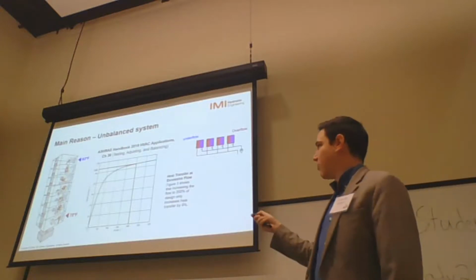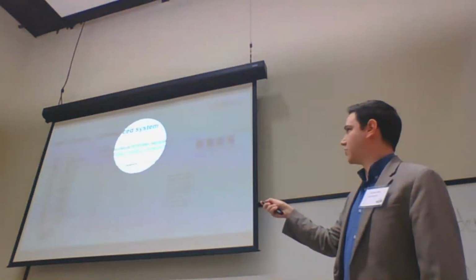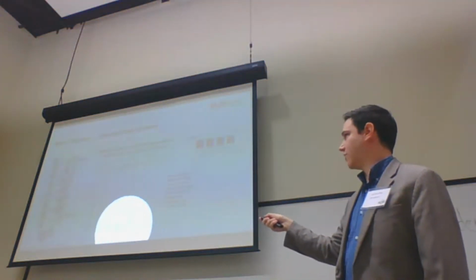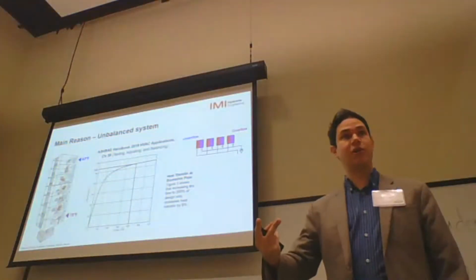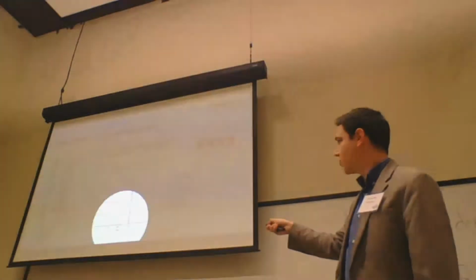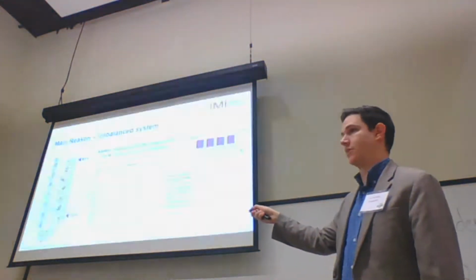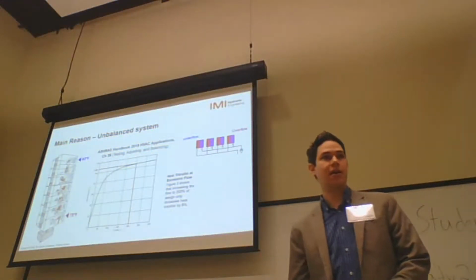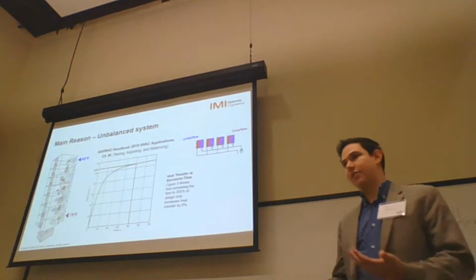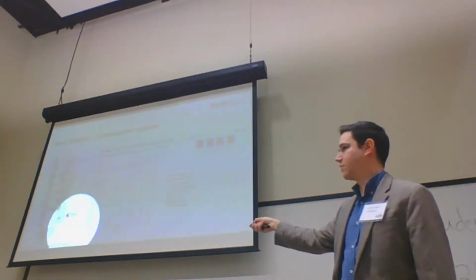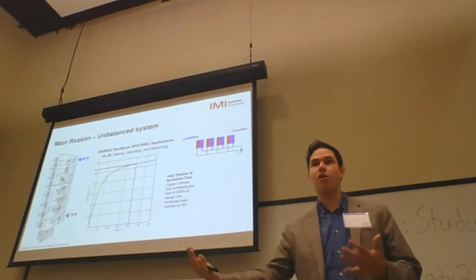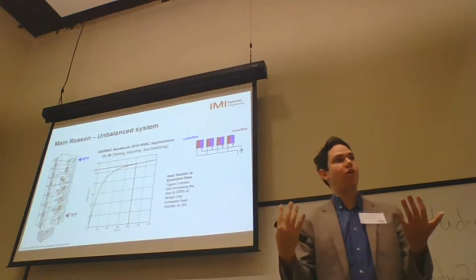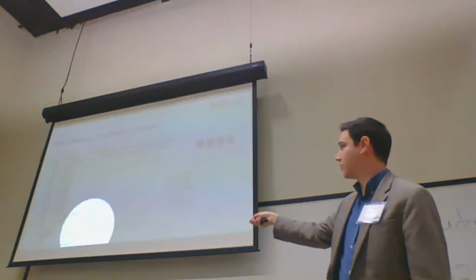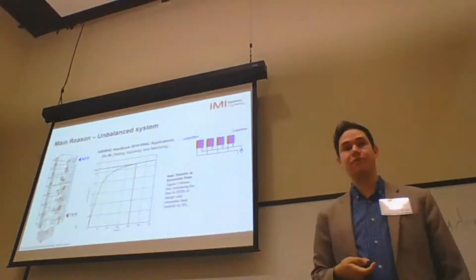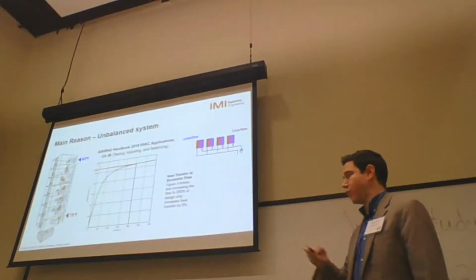Another important point to highlight: when you look at the ASHRAE Handbook 2019, Chapter 38, if you get 200% of the flow, or 2 times the design condition of that coil specifically, you're only increasing the heat output by 6%. In other words, it's just a waste of energy getting a higher overflow in the coil. That works for heating and cooling. But this graphic, this curve right here, is more specifically for coils where you have heat transfer between water and air. If it's between water and water, it is a linear output between flow rate and heat output. So there's no benefit of overflowing the coil.